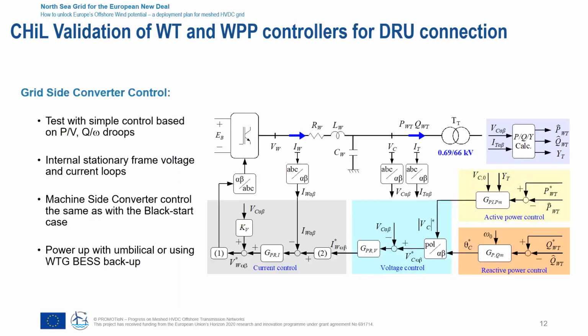The controllers that have been used for testing the complete system are based on P/V, Q/omega droops. They have internal voltage and current loops, and the machine side converter control is the same as that which has been done for the black start operation and is in charge of keeping constant the DC link voltage. The power up of the whole system is carried out either using an umbilical HVAC cable or using local energy storage in each one of the wind turbines.